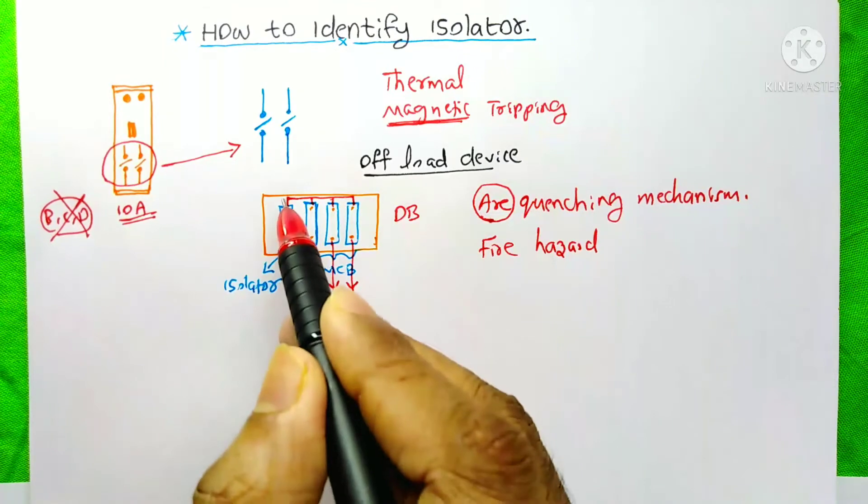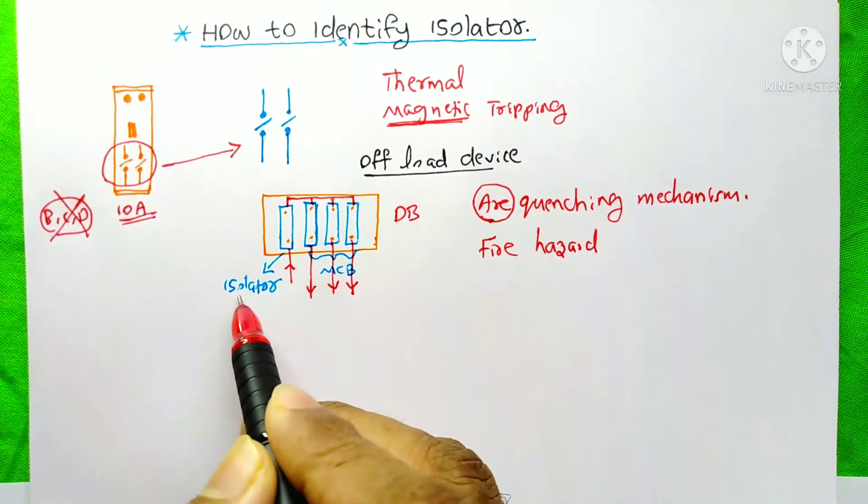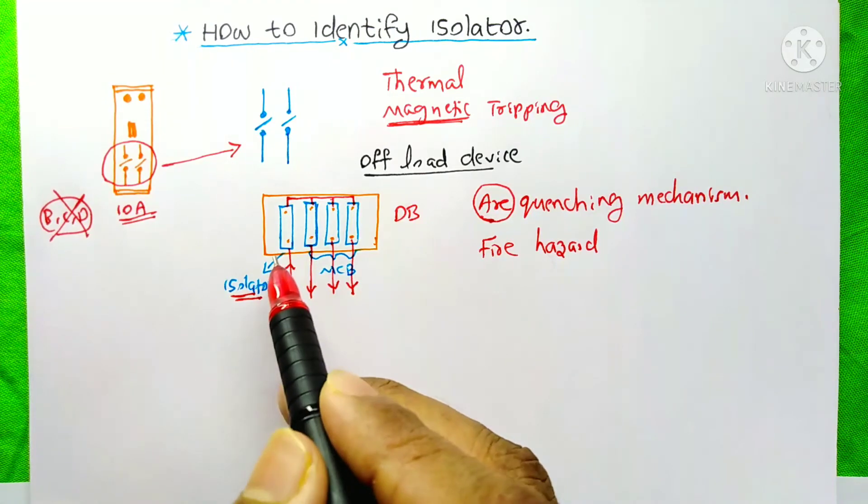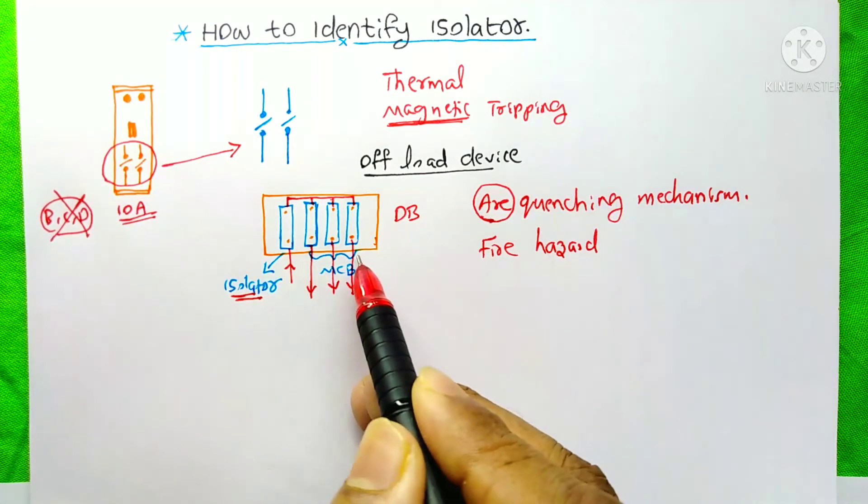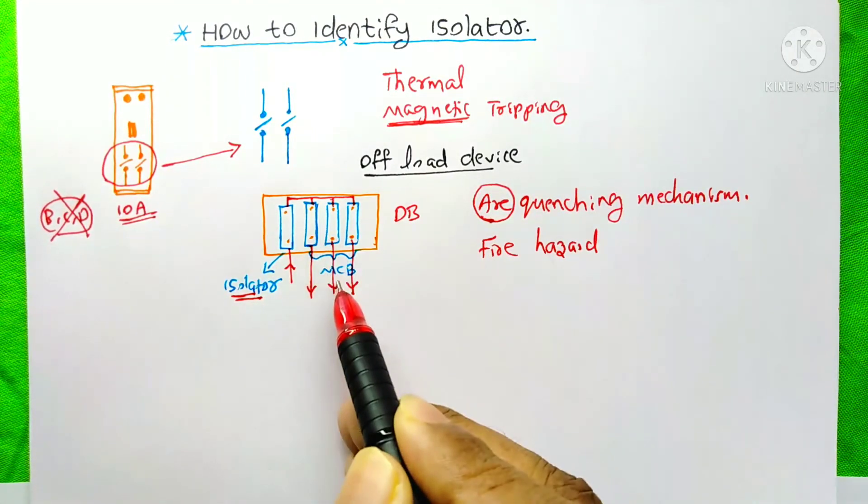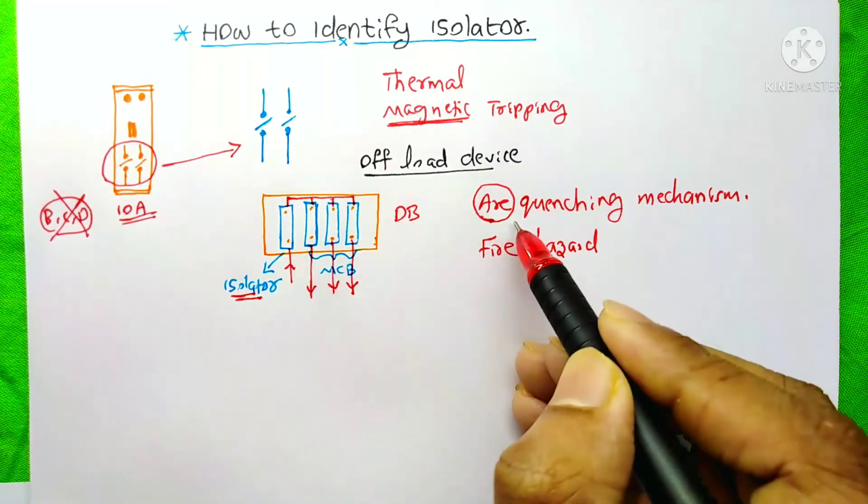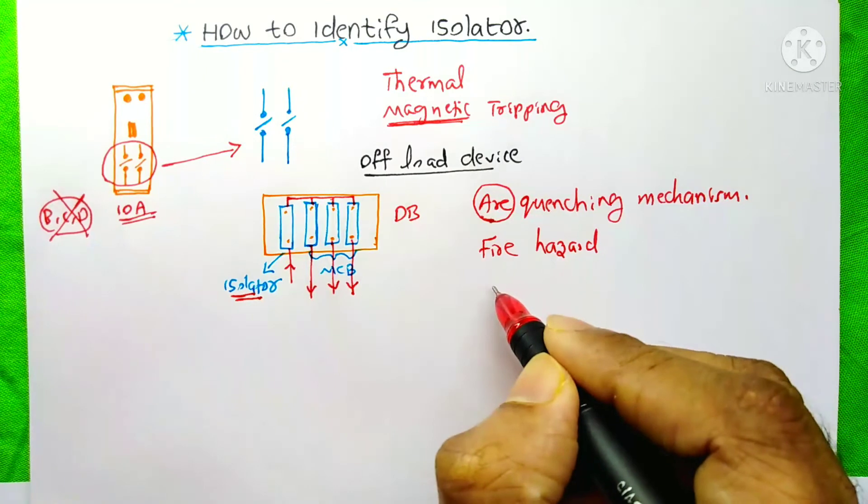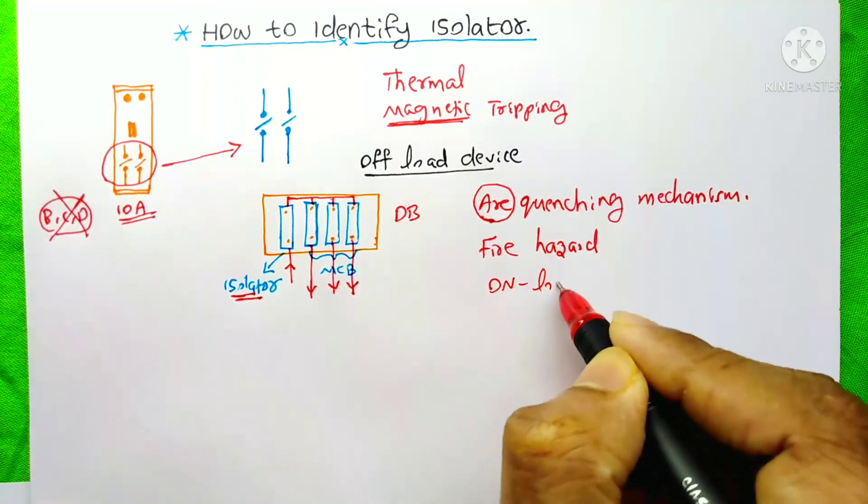But if there is an MCB is on the place of this isolator, then you can easily switch off your main breaker without switch off these MCBs. Because the MCB has the arc quenching mechanism. So we can call the MCB as an onload device.